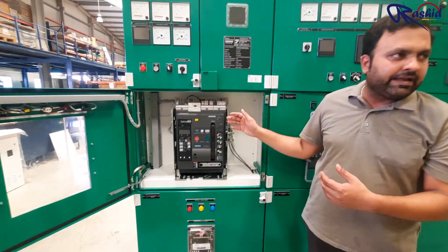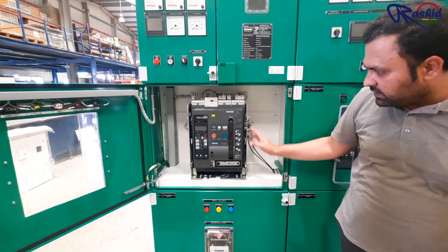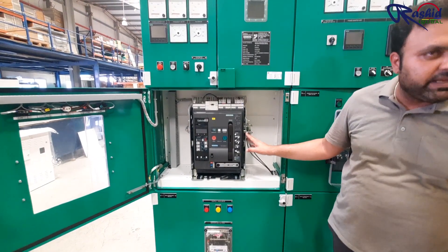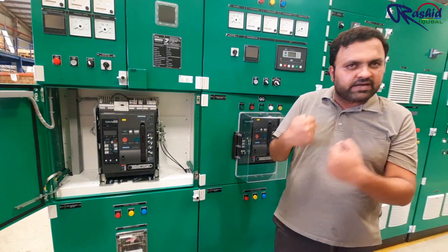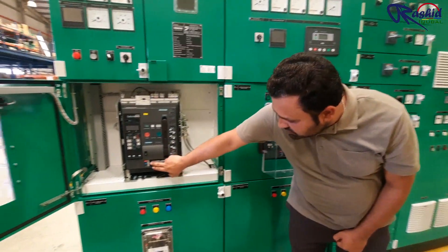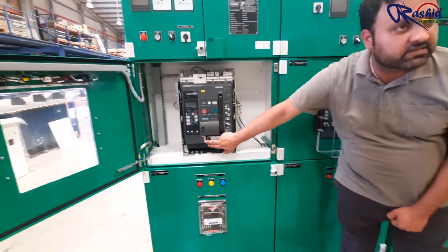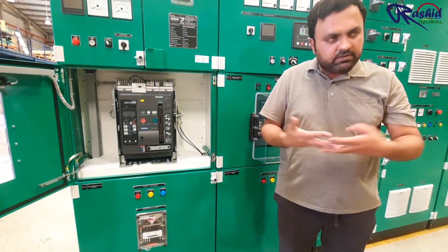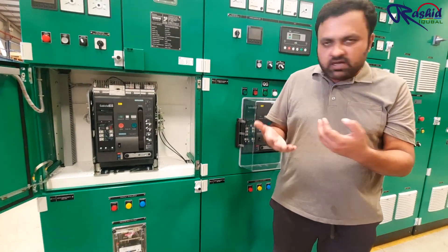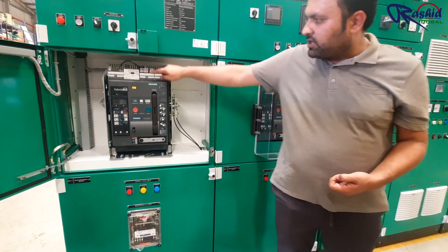Related to that, it has many safety features. Right now this is in the connect position, meaning our ACB terminals are connected to the bus bar and it is ready for operation. You have a position indicator which shows connect, test, and disconnect. Connect means the ACB is fully connected to the terminal; test means the main contacts are disconnected but the control is connected.